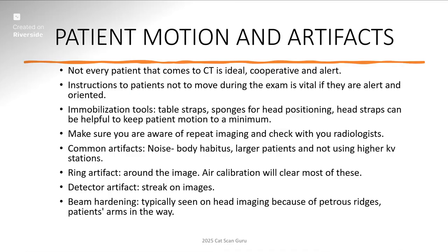So what I did is I said, okay, let's not send for anybody because it's going to take 20 minutes. And I went ahead and ran another air calibration test. And all of a sudden the ring artifacts are gone. And the tech tells me, oh, well, I just leave the phantom. I was like, you can't leave the phantom in there. You have to actually bring the table all the way out to do the air cal because that's the whole purpose of it. So make sure you don't have anything inside the gantry when you're doing an air calibration test, okay? Because then you'll minimize the ring artifact.